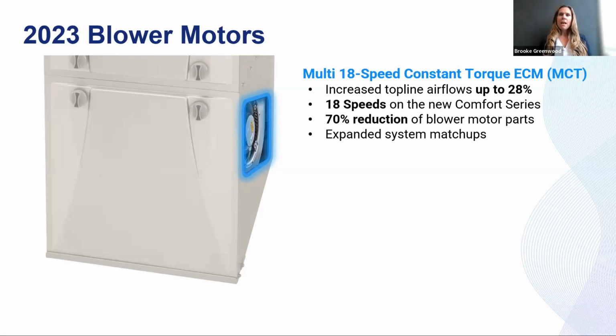This strategy also allows us a significant reduction in service parts. Today, that 5 fixed-speed motor has its programs housed in the motor module itself, meaning every unique SKU or model number has a very specific motor part number with airflows specific to that unit. With this new strategy, our airflows will actually be housed in our control board.